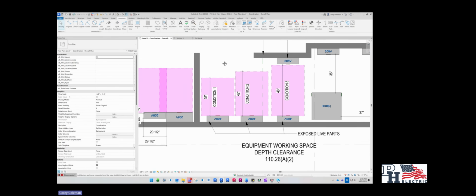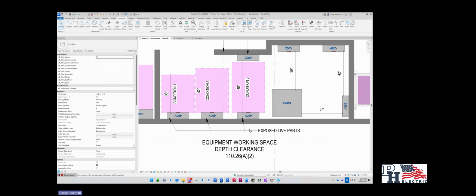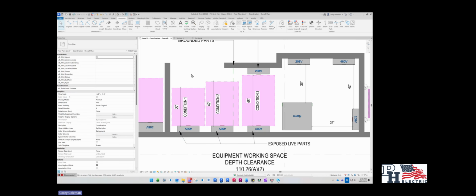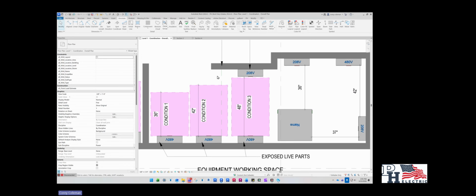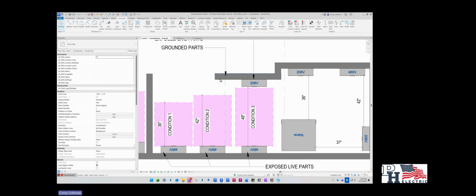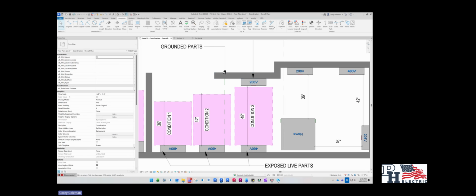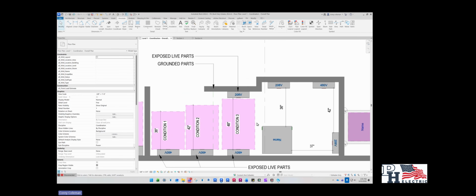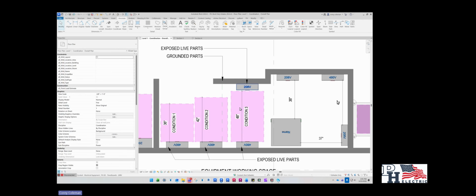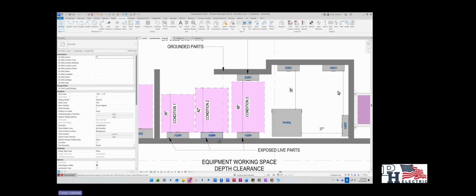Awesome. So moving on, we're going to go on to the depth clearance of working spaces. And this one goes into variable conditions based on what is opposite of the panel as well as the voltage of the panel. So first we have condition 1, which is if there are no exposed or grounded parts in front of the panel, so that would be just open space. Condition 2 is if there are grounded parts in front of the panel. Grounded parts are usually considered brick walls, tiles, any type of wall in front of it with no electrical equipment. And then condition 3 is when you have exposed live parts facing exposed live parts. That gives you the largest clearance that you need here.